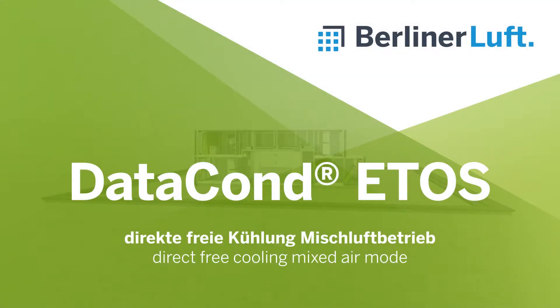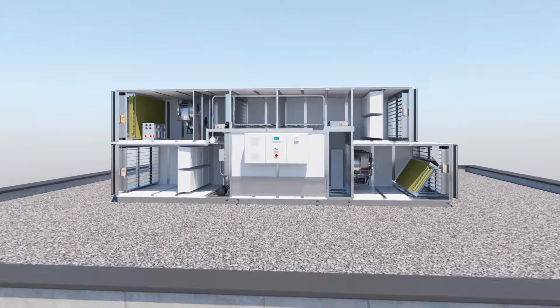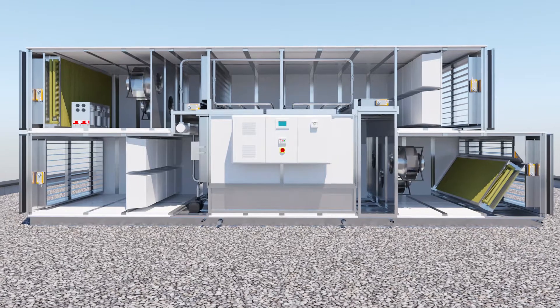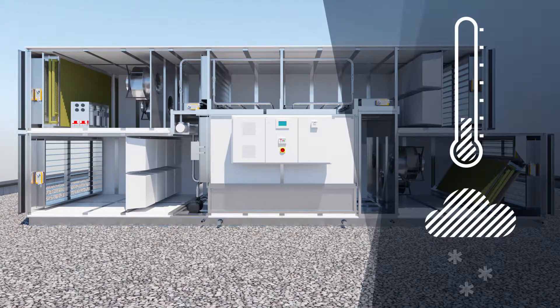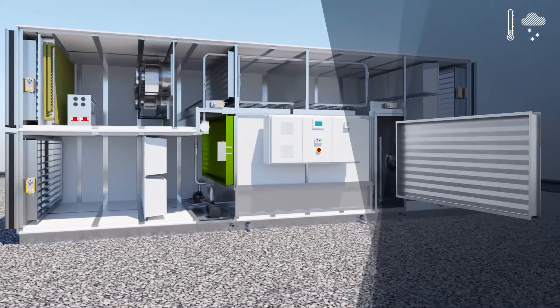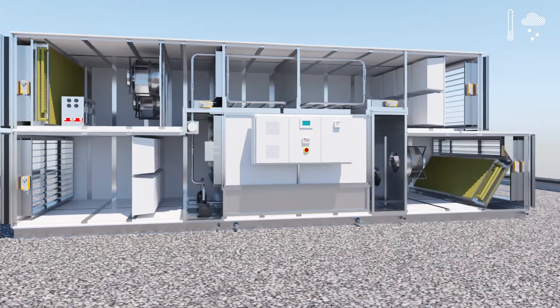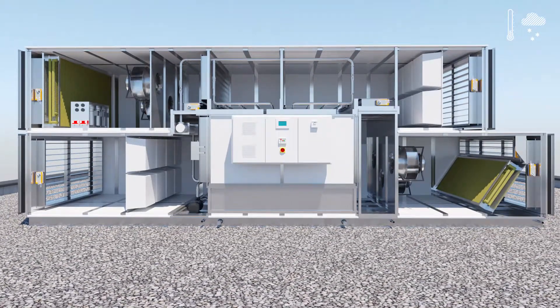Another operating mode of the DataCond ETOS is direct free cooling mixed with recirculated air. In typical winter conditions, the exhaust air fans automatically reduce speed. To reach the ideal air conditioning temperature, the damper on the plate heat exchanger is gradually opened.